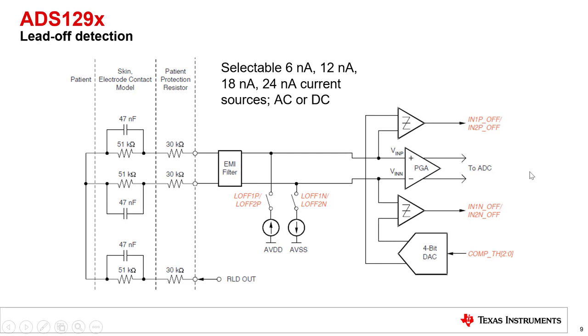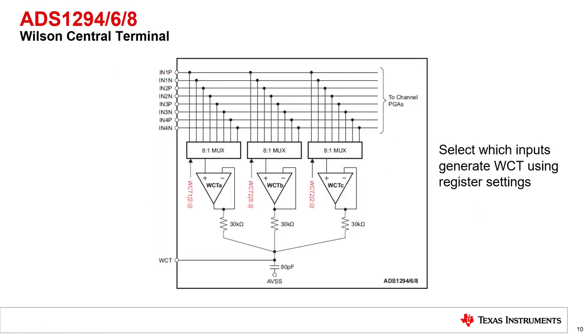In the ADS1294, 6, and 8 devices only, three buffer amplifiers are also integrated to generate the Wilson Central Terminal, or WCT. The circuit allows the user to pick the three limb leads from any of the electrode inputs using a register configurable mux. Each electrode is buffered and connected to a resistor summing junction to obtain the WCT voltage, which will be output onto an external device pin.